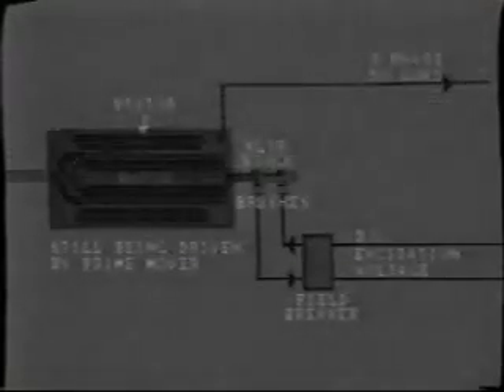level. But what would happen if the generator did suffer a complete loss of field, perhaps due to a defect in the excitation circuit? In this situation, remember, the generator is still connected to the power system and still delivering megawatts because it is still being driven by its prime mover. However, it will no longer supply VARs. On the contrary, it will draw VARs from the system in order to maintain excitation. The power factor will move to, say, 0.5 leading. So the generator will continue running and producing power as an induction generator.